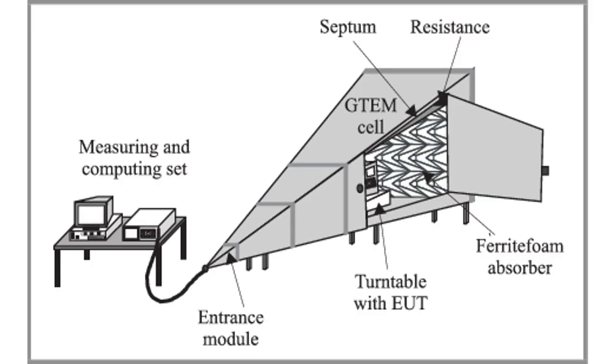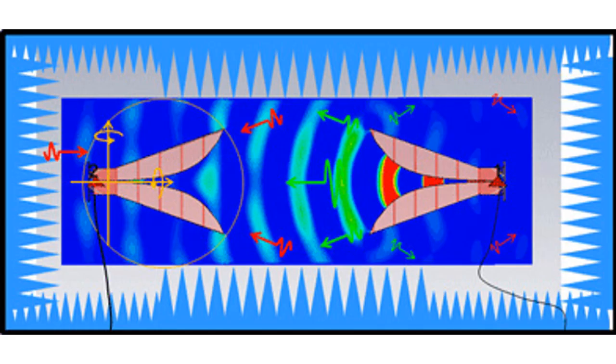Test cells such as the GTEM are highly efficient but restricted to small products. Screened chambers can be large, but can be relatively expensive and require powerful amplifiers to create the required stress levels.